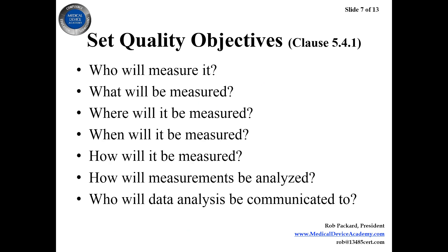If you're going to set quality objectives, the clause in the ISO standard is clause 5.4.1. The key elements for a good quality objective are: who will measure it, what specifically will be measured, where will it be measured, when and at what frequency, how — what tools will be used, whether an automated report or visual observation, how will it be analyzed (graph, t-test, run chart, log or linear plot), and who will the data analysis be communicated to. If the data just sits in a folder at your desk, that doesn't meet the requirements of a quality objective — it has to be communicated to the rest of the company.